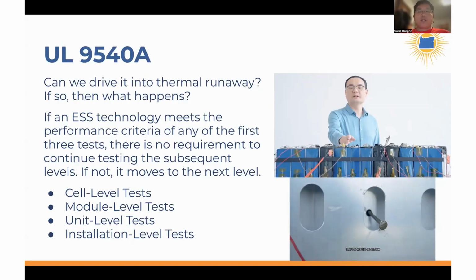If it doesn't, then you're not required to move to subsequent tests. So if there's inherent safety at the cell level, there's not necessarily a requirement to do further testing at the module or unit level. But if it's not super safe at the cell level, they'll advance to module level safety - so if one cell actually does vent gas, does that gas then cause the cells next to it to also vent, creating a domino effect? If it doesn't, then maybe it's inherently safe at the module level. 9540A does that kind of testing.